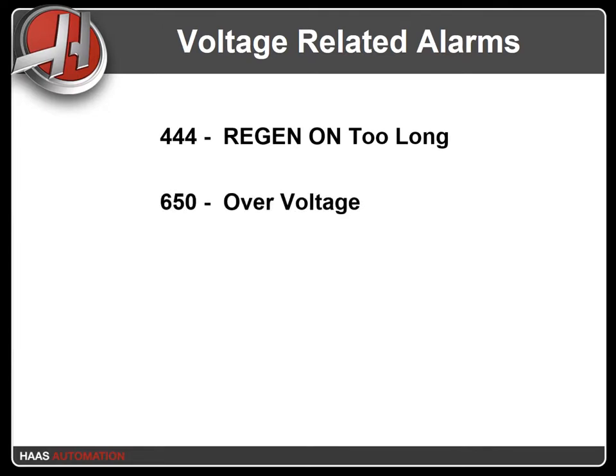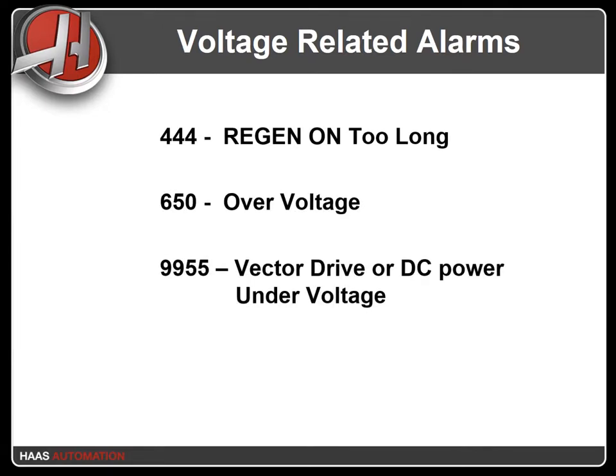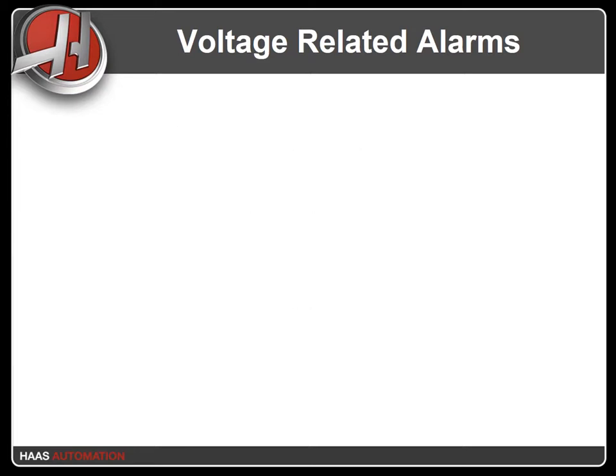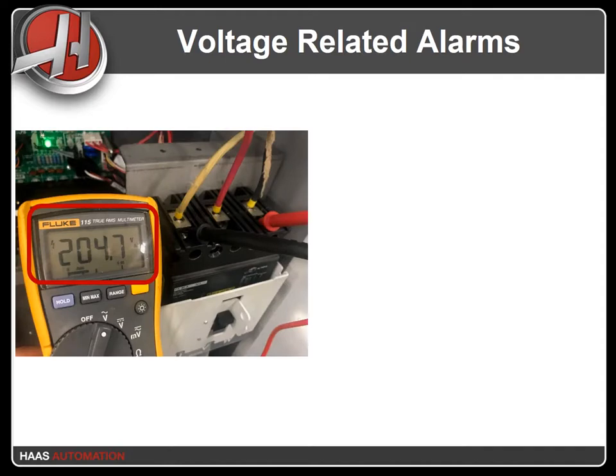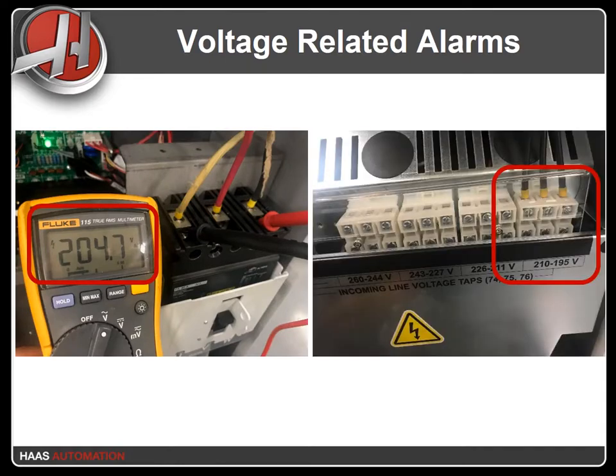Alarms 444 regen on too long, Alarm 650 over voltage, and Alarm 9955 vector drive or DC power under voltage are most of the time caused by issues with the incoming AC power or an incorrectly tapped transformer. The first thing to do for a voltage-related alarm is to measure the incoming AC voltage — measure leg-to-leg and leg-to-ground. Make sure that the transformer is correctly tapped based on the incoming power. Lines connected to the incorrect tap cause either too high a DC bus or intermittent low voltage conditions.